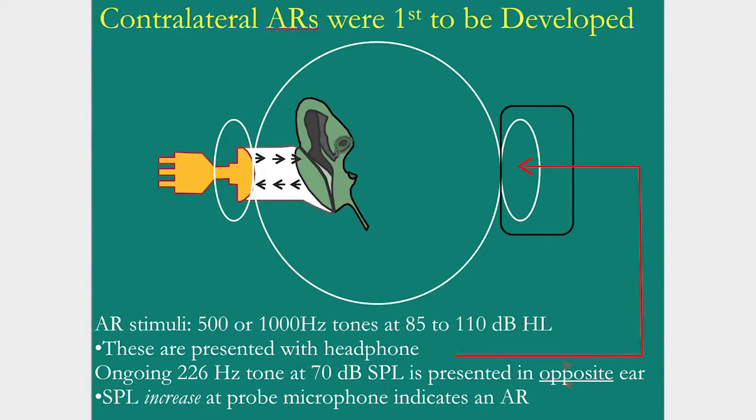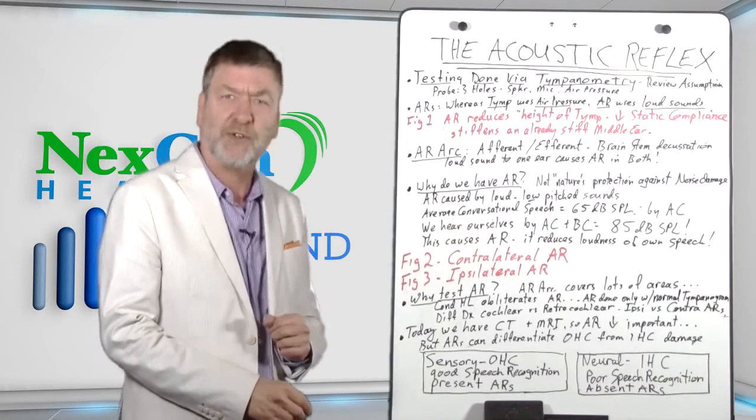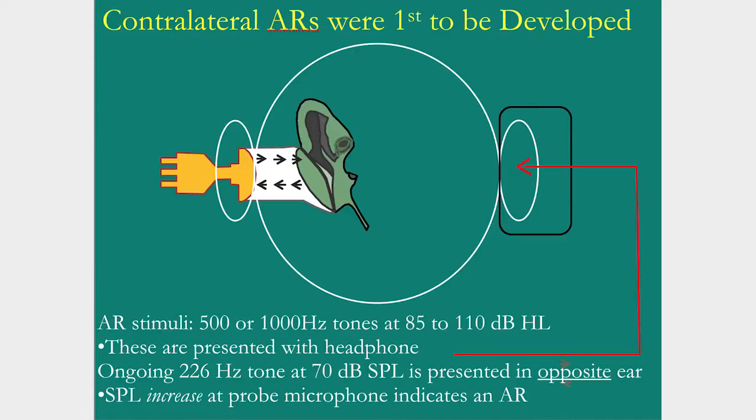Figure two, let's look at two different ways that the acoustic reflex is measured. Figure two shows the contralateral method of measuring the acoustic reflex. Figure three shows the ipsilateral method of testing the acoustic reflex. First, figure two, contralateral. This involves the tympanometer probe stuck in one ear, sealed with its three holes, the speaker emitting the constant low-pitched tone at 70 dB SPL.